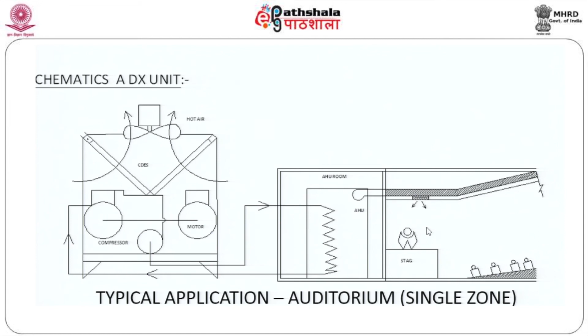You can see hot air here. So this is kept at about maybe 70 degrees centigrade. 40-degree air goes inside, cools this coil, and hot air gets rejected. This circuit of hot air has absolutely nothing to do with this circuit, which is drawing 24 degrees air, cooling it down by an 8-degree media to about 12 to 13 degrees when it is discharged here.